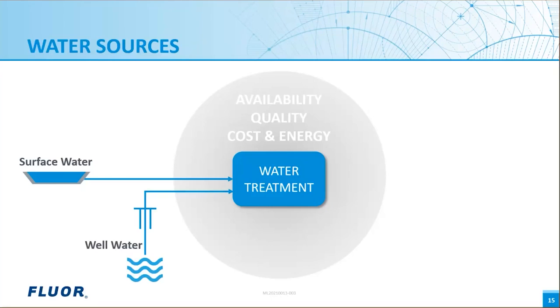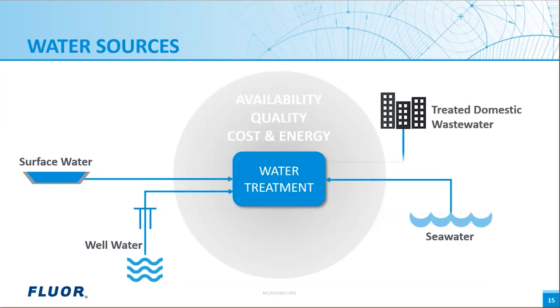Well water can range from fresh water with very little suspended solids and organics to brackish water with a wide range of both. Brackish water may be more available, but will be more expensive to treat compared to fresh water. Significant treatment is required prior to removal of dissolved material. High dissolved solids concentrations translates to high energy requirements and potentially high waste disposal cost. Seawater will require similar treatment to brackish water to remove salts, but it will be more costly and energy intensive. Benefit being that it is available in significant quantities.